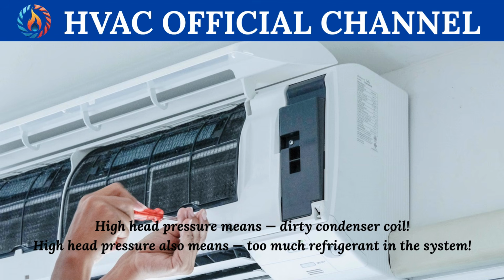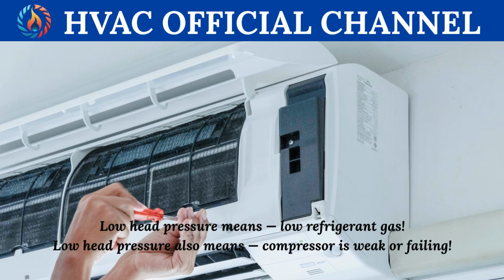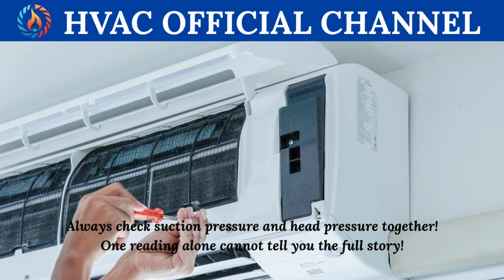High head pressure means dirty condenser coil. High head pressure also means too much refrigerant in the system. Low head pressure means low refrigerant gas. Low head pressure also means compressor is weak or failing. Always check suction pressure and head pressure together. One reading alone cannot tell you the full story.